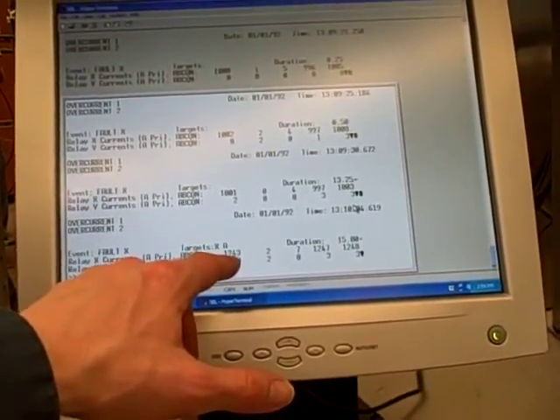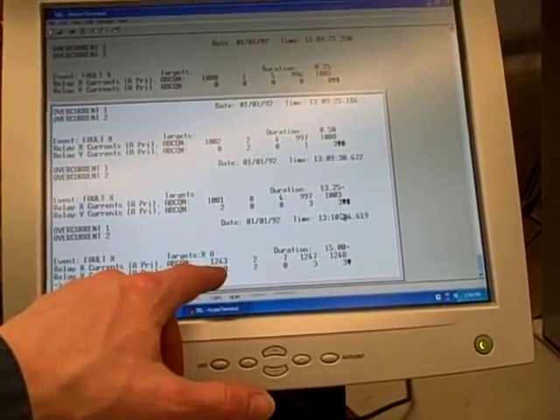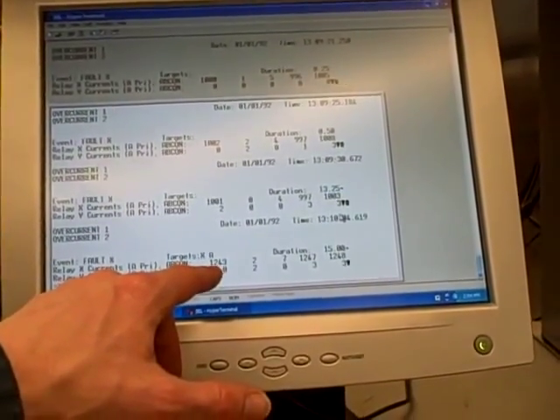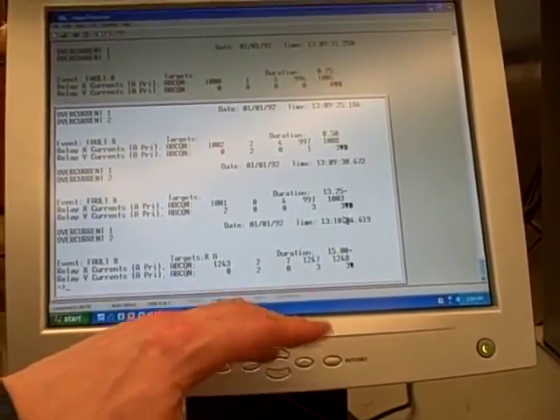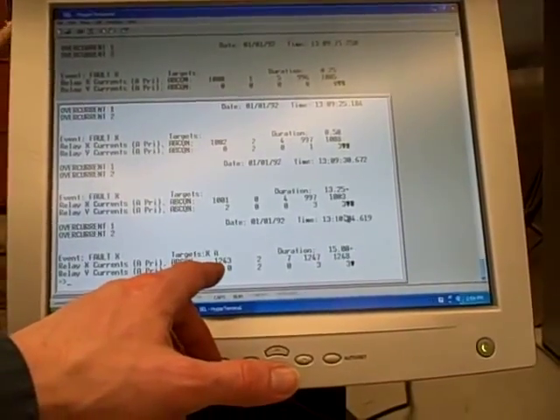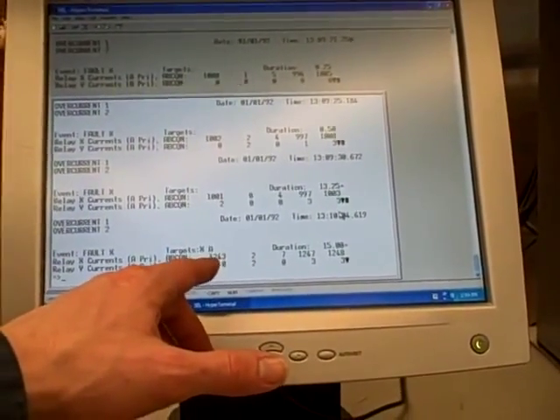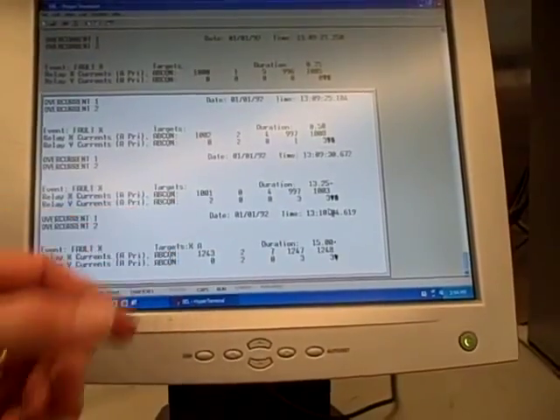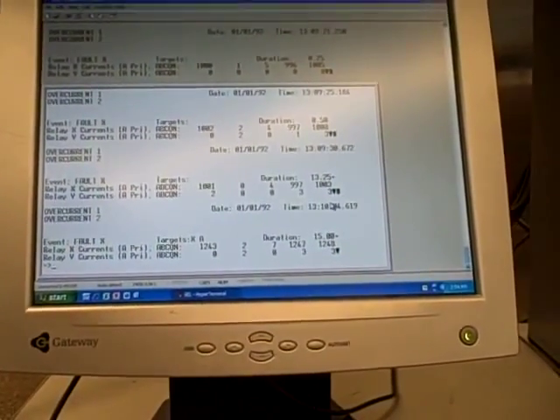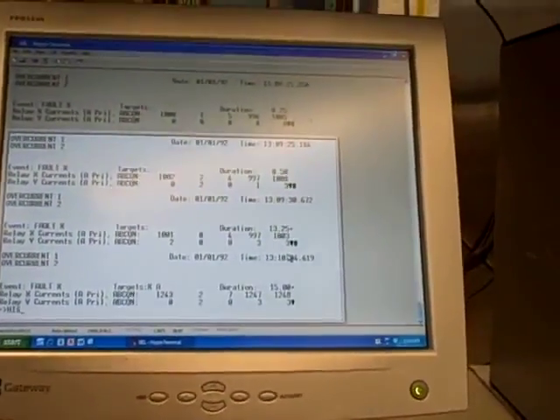the trip, 1,243 amps. Remember, my pickup value for the overcurrent was 5 amps on the secondary of the CT, which was 1,000 amps on the line, the power line. And so we're well over our pickup current, and so it sat there at that amount of current until it finally tripped. I can also take a look at the history of recent events.